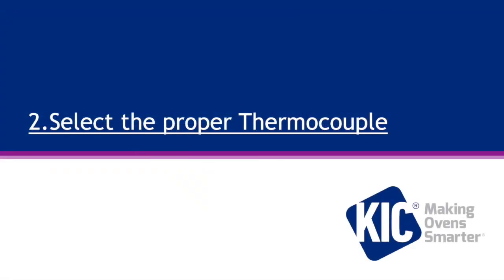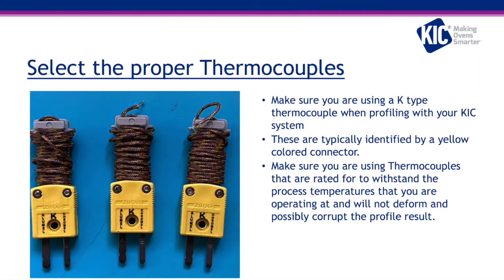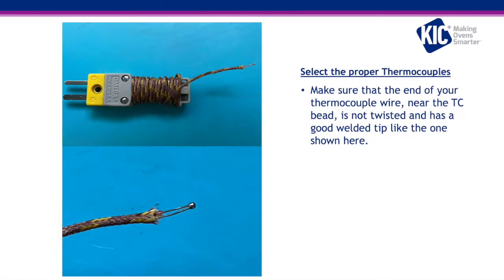Select the proper thermocouples. Make sure you are using a K-type thermocouple when profiling with your KIC system. These are typically identified by a yellow colored connector. Make sure you are using thermocouples that are rated to withstand the process temperatures that you are operating at and will not deform and possibly corrupt the profile results. Make sure that the end of your thermocouple wire near the TC bead is not twisted and has a good weld tip like the one shown here.